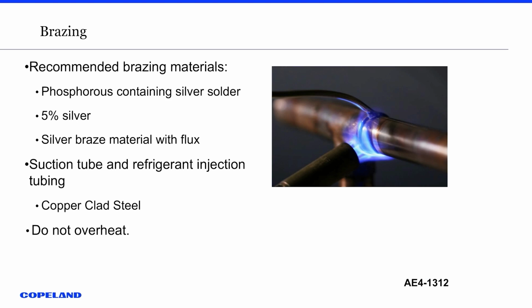The other thing I wanted to point out with our scroll compressors, it's a copper clad. So if you overheat it, that cladding will go away. So you have to use a higher silver content brazing material to connect your pipe into, because it'll be steel then, right? So be careful whenever you're brazing. Do not heat up fittings to disconnect them. Always cut them out, whatever it is in the system.